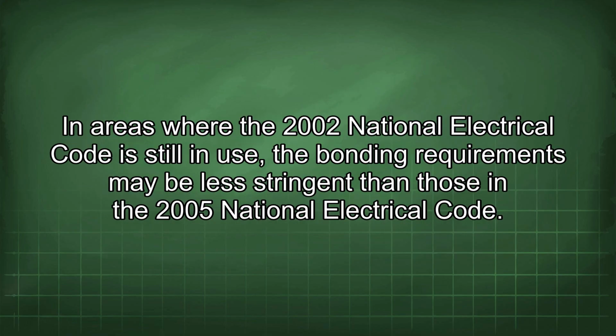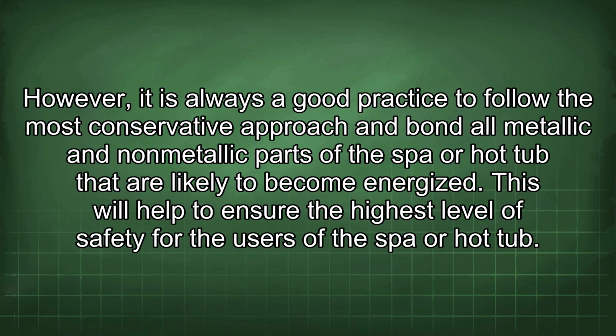In areas where the 2002 National Electrical Code is still in use, the bonding requirements may be less stringent than those in the 2005 National Electrical Code. However, it is always good practice to follow the most conservative approach and bond all metallic and non-metallic parts of the spa or hot tub that are likely to become energized. This will help to ensure the highest level of safety for the users of the spa or hot tub.